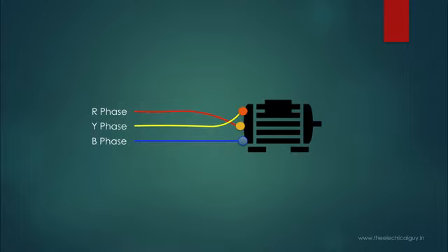change. Why is phase sequence important for induction motors? Because the direction of rotation of the motor can be changed with a change in phase sequence. So if your motor is running in the opposite direction, phase sequence could be one of the causes. If your three-phase load is purely resistive, then a change in phase sequence will not affect anything. But it may affect unbalanced inductive or capacitive loads.